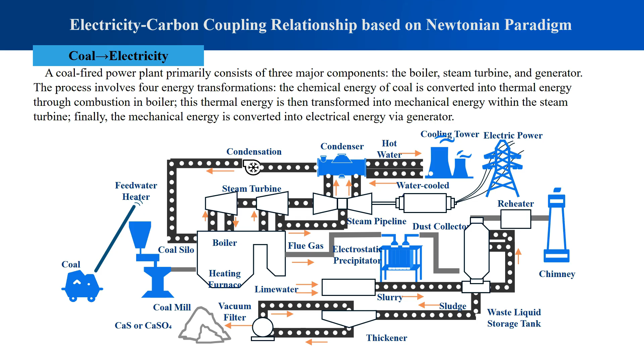The main equation expresses generation output as fuel consumption multiplied by lower heating value and by the conversion efficiencies of the plant. B is the coal consumption rate. Q net P is the lower heating value of the fuel. Eta B is boiler thermal efficiency, eta P is pipeline efficiency, eta I is the absolute internal efficiency of the steam turbine, eta M is mechanical efficiency, and eta G is generator efficiency. The factor 1/3600 converts heat energy into electrical energy units.